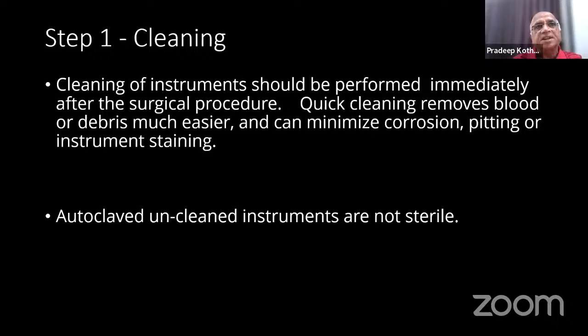Then you will be able to remove all the blood clots and debris from the instruments. Quick cleaning removes blood and debris much more easily and can minimize corrosion, pitting or instrument staining. Autoclaved, uncleaned instruments are not sterile, so they have to be cleaned properly. Gadgets like ultrasonic cleaners are available. They produce microscopic bubbles that collapse. This cavitation process is very effective in getting into serrations, box locks and crevices of the instruments and cleaning them properly.